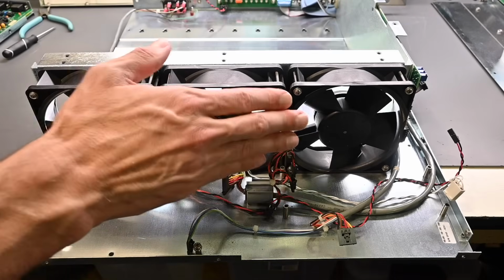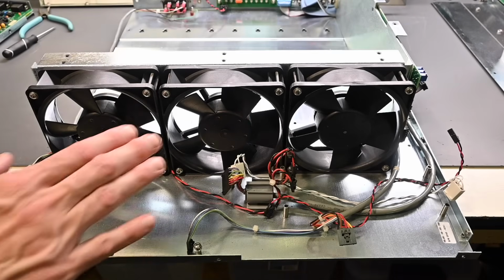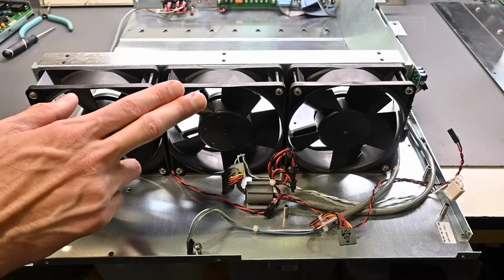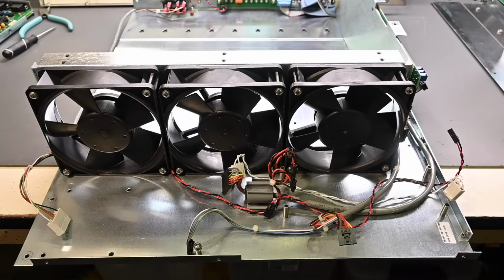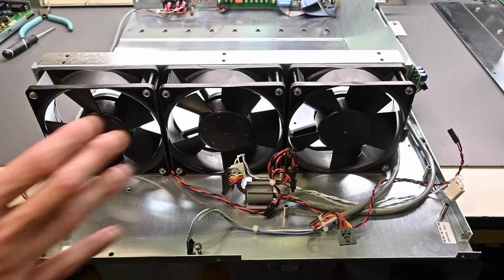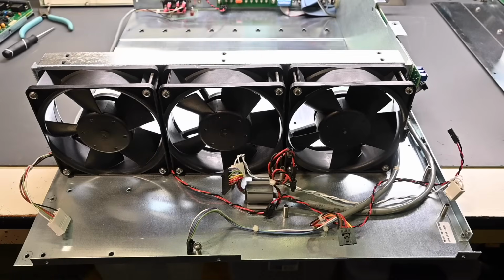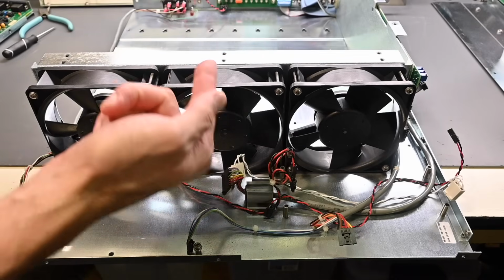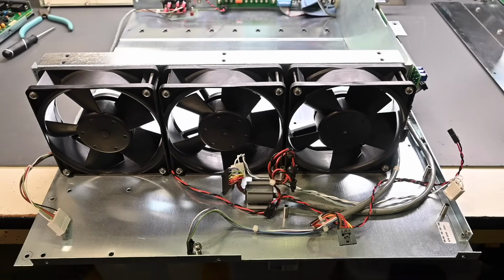Now these are 24 volt brushless motors, and there's some control circuitry, and these run on less than 24 volts for the low speed, and that voltage is increased if more cooling is needed. So there's a big vent in this front corner, and also a vent across the top of the instrument, and air is drawn in this way, goes through the fans, and exhausts out the back.